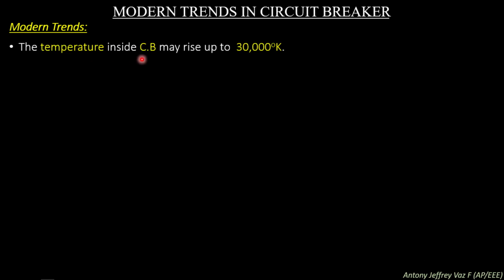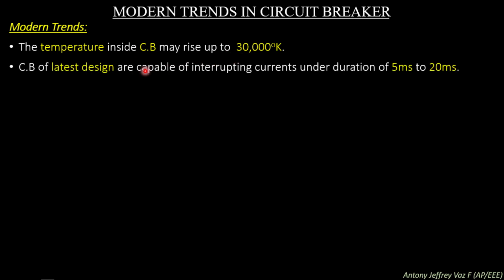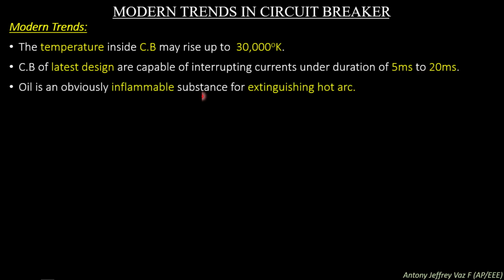The temperature inside a switchgear or circuit breaker may rise up to 30,000 degrees Kelvin. Circuit breakers of the latest design are capable of interrupting currents within a duration of 5 milliseconds to 20 milliseconds. Oil is an obviously inflammable substance for extinguishing a hot arc. So, in our latest designs, the interruption of current should be made within a duration of about 5 to 20 milliseconds. We know that this is a very short duration, so the circuit breaker should interrupt the short circuit current within a minimum period.